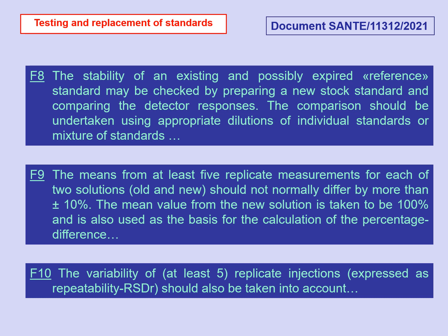The means from at least five replicate measurements for each of two solutions — old and new — should not normally differ by more than ±10%. The mean value from the new solution is taken to be 100% and is used as the basis for calculating the percentage difference. The variability of at least five replicate injections, expressed as repeatability RSDR, should also be taken into account.